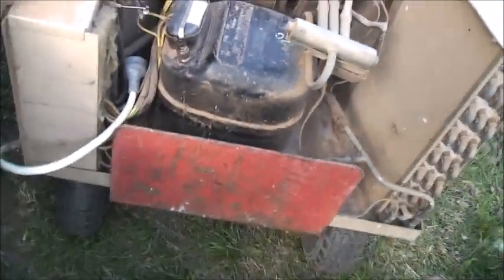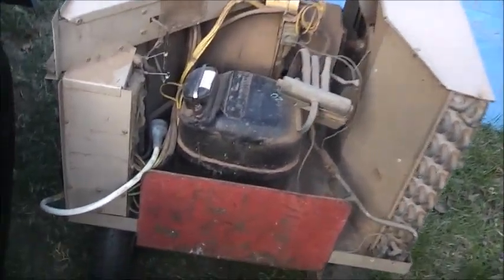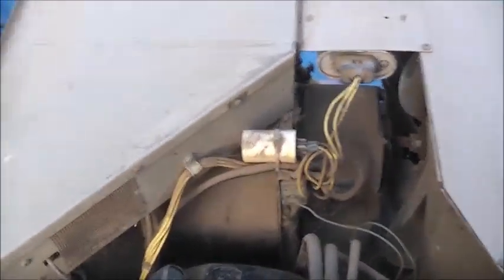Anyway, let's get this vac down and on the pump for a while, get it nice and emptied out completely before I put my R152a in it. Okay, we'll fire up the valve. We'll set the residual pressure about 10 psi, and we'll completely vac that down. I'm confident that weld's gonna hold pressure. I got that proper cherry red. I'm confident it's a good weld.